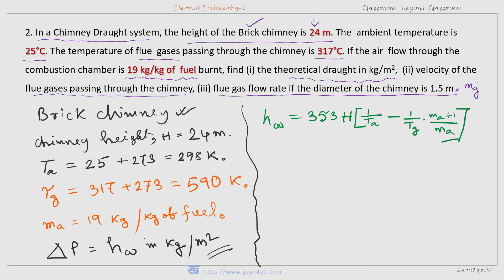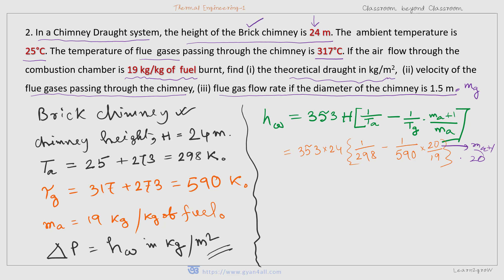We'll use the formula: Hw equal to 353H multiplied by (1/Ta minus 1/Tg) multiplied by (Ma plus 1) upon Ma. Putting the values H, Ta, Tg, and Ma — with 298, 590, and 20 by 19, where 20 is Ma plus 1 (that is 19 plus 1) — we get the theoretical draught. Simplifying, we get 13.3 millimeter of water, which is the theoretical draught.